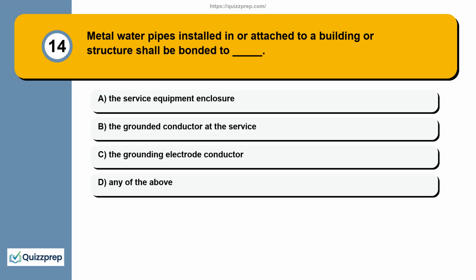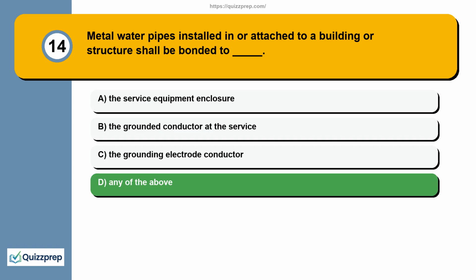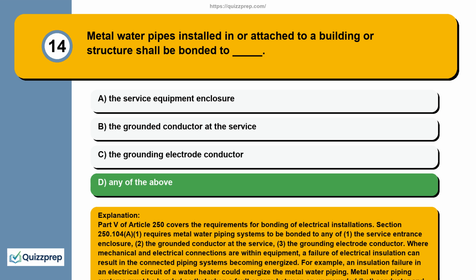Question 14. Metal water pipes installed in or attached to a building or structure shall be bonded to the service equipment enclosure, the grounded conductor at the service, the grounding electrode conductor, any of the above. Part 5 of Article 250 covers the requirements for bonding of electrical installations.